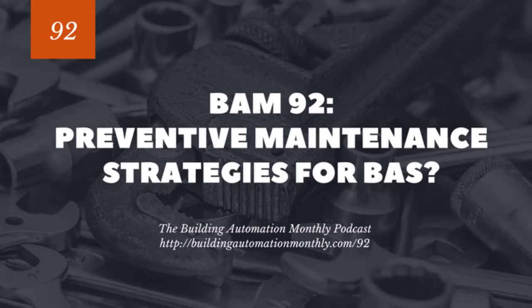So when I start to think about the first kind of preventative maintenance action you should take, you should definitely come up with a regular schedule to back up your databases. For me, I usually have the general rule of having a backup every time something major changes. So if I do a retrofit or some major retro-commissioning or adding of devices, those kinds of things, I'm going to do a backup.